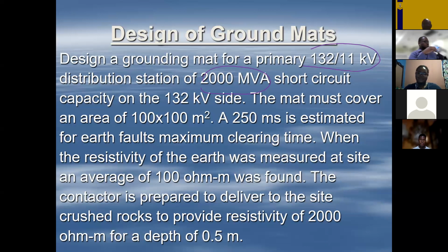So you'd have the system, and the systems you'd be engaging with have models of it, so obviously you wouldn't be doing it on the actual system. You have the short circuit capacity, the area in terms of the substation size, and the 250 milliseconds estimated for earth fault maximum clearing time, which you would have determined using your stability analysis. That's the maximum clearing time: how long can you have the fault on the system without the system dropping.